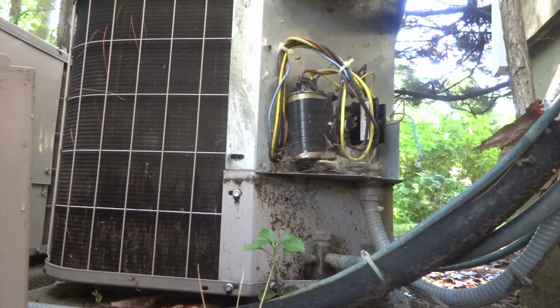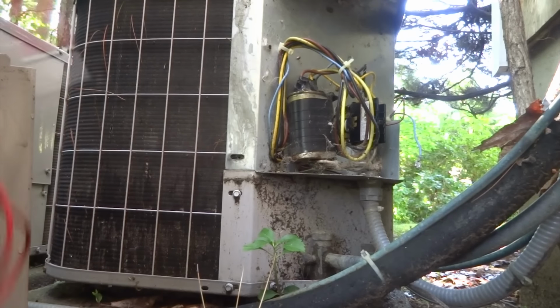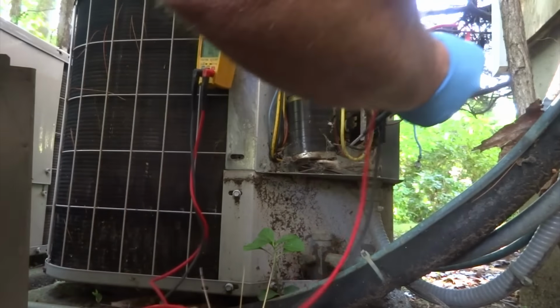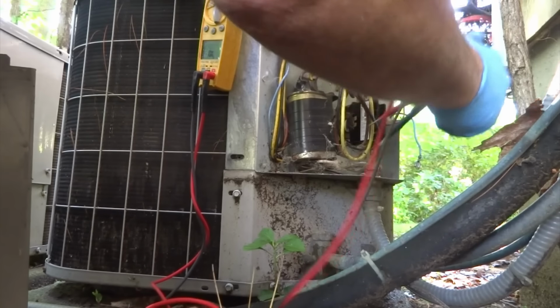It should be 14 ohms. If it's low, that's a direct short to the transformer upstairs, and that would have blown that transformer too, because of the voltage. So I've got the ohms right here, let's see what it is. I've got my power off.